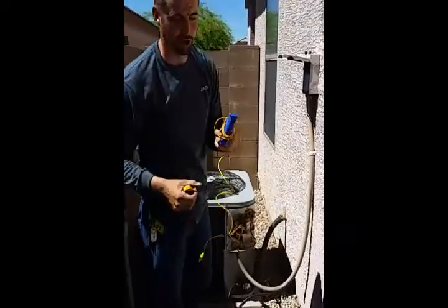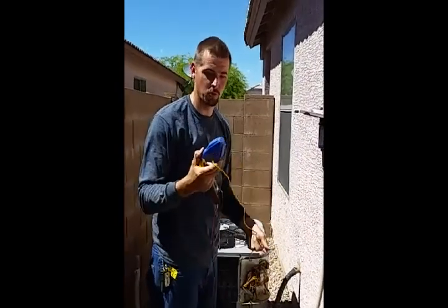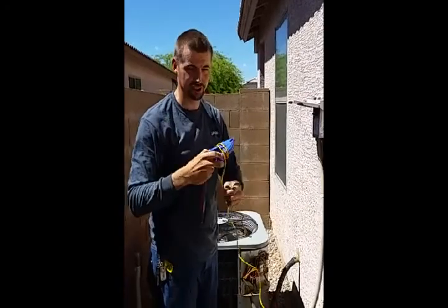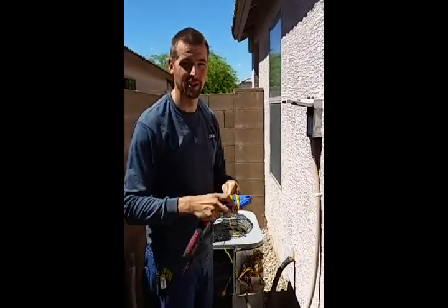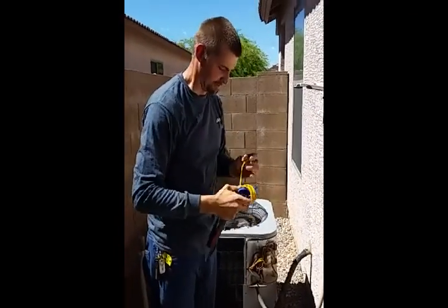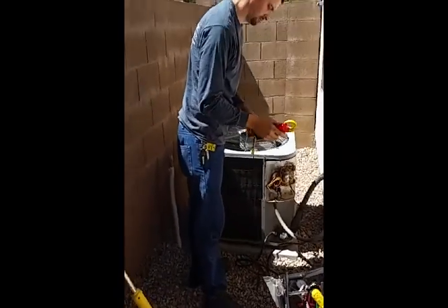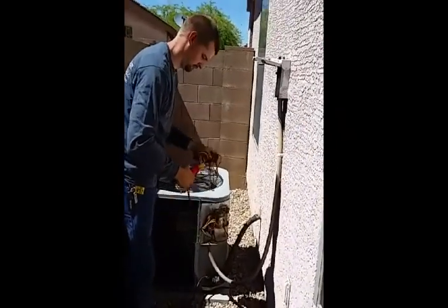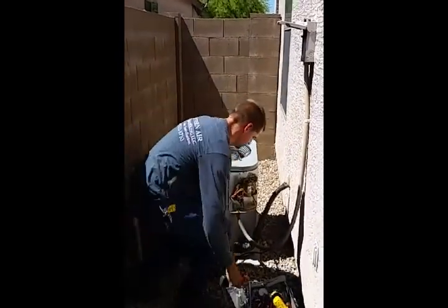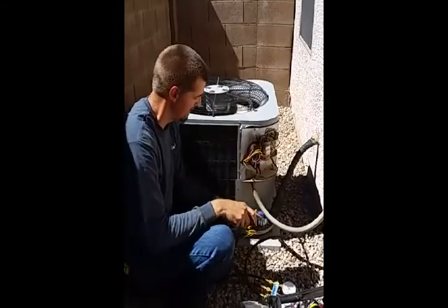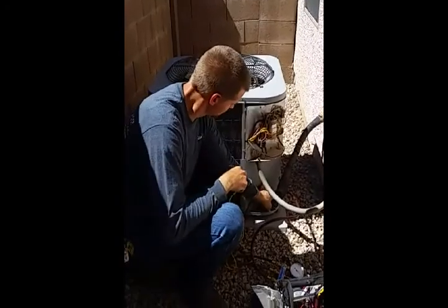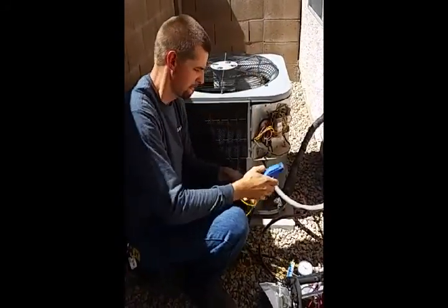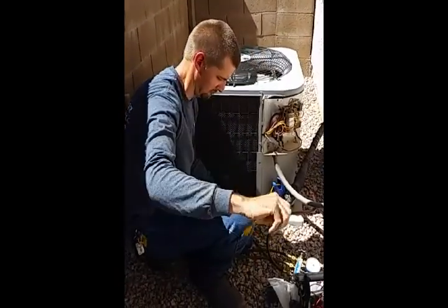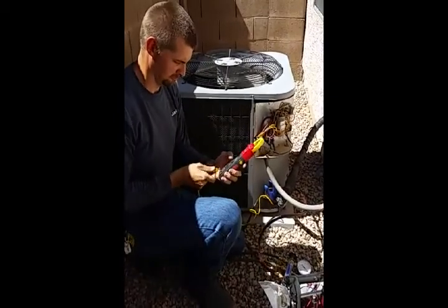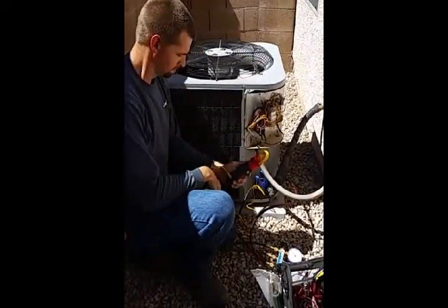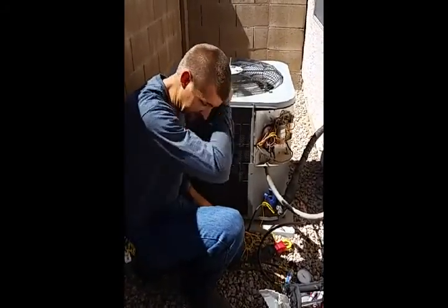Now what this is, it's a temperature clamp. And this temperature clamp basically will tell me what temperature my suction line is. Your suction line is your line coming back from the air handler to the condenser. Okay, what you want to do is clear yourself a spot here. Get a good reading. Sit for just a minute and stabilize.